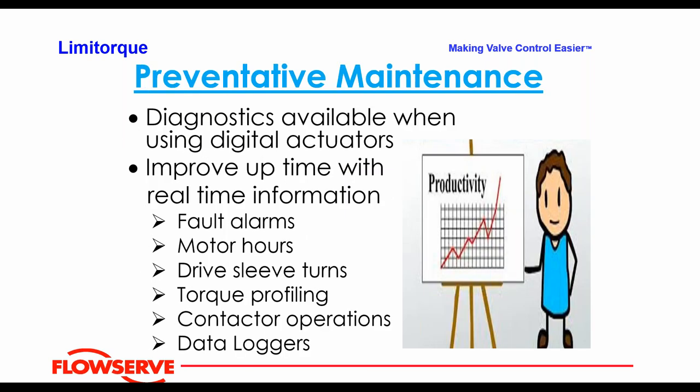Regarding preventative maintenance: in an era where a lot of equipment has controllers and computers on board, these actuators can tell you a lot more about your valves than was possible in the past — everything from fault alarms, motor hours, drive sleeve turns, torque profiling, contact ops (number of cycles), and data loggers — all of which allow plants to fine-tune their predictive maintenance and maintenance schedules.